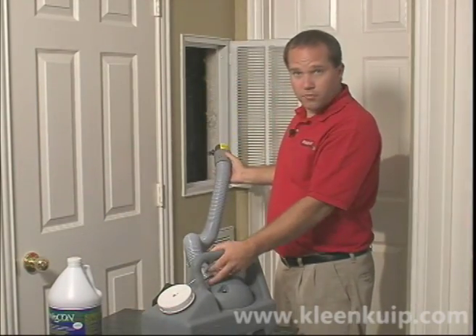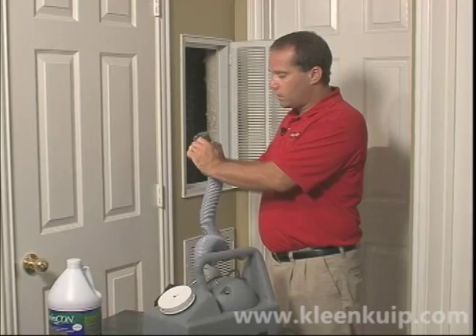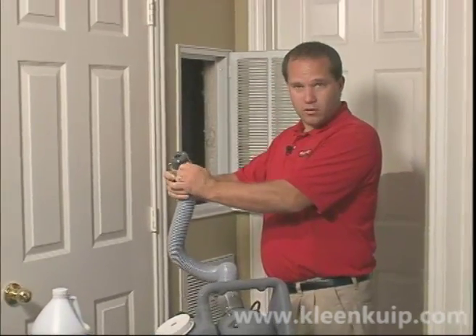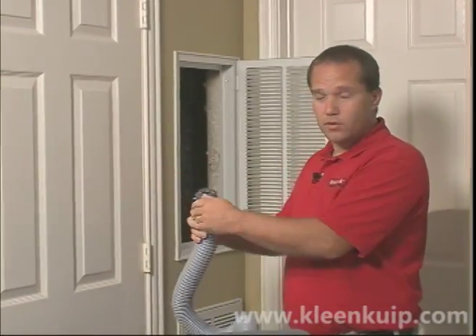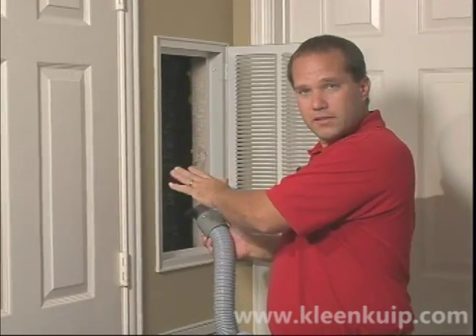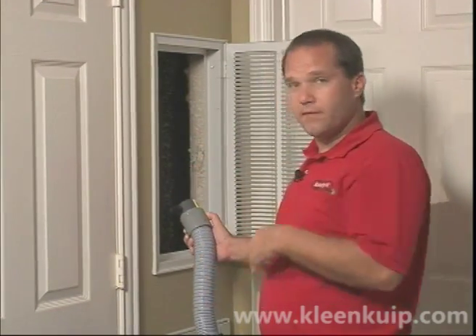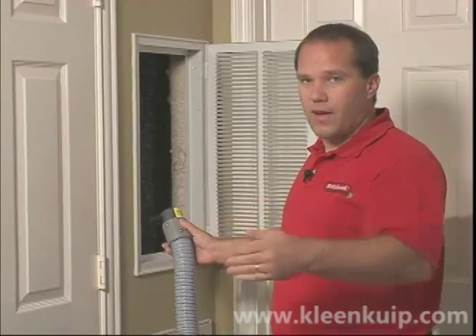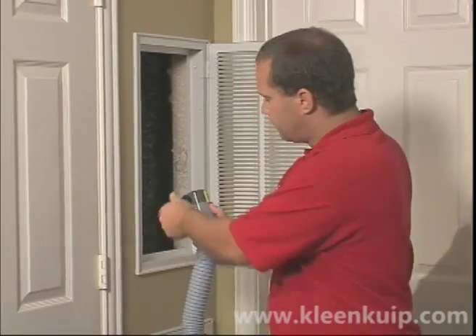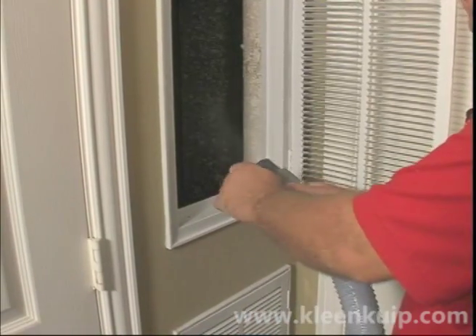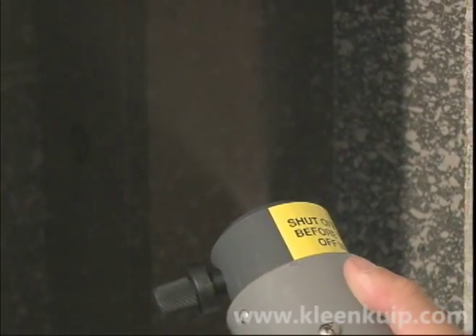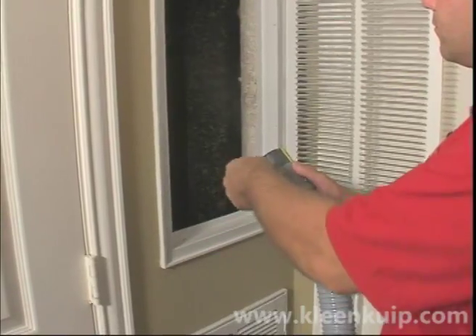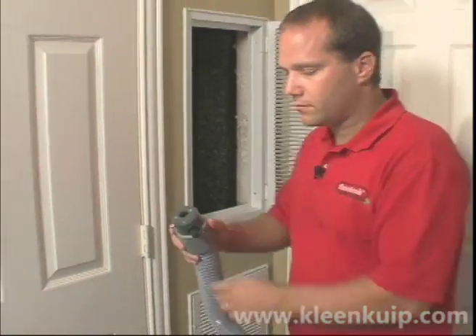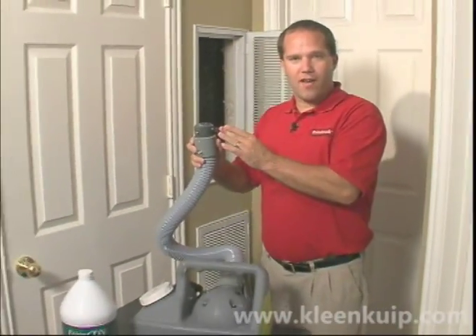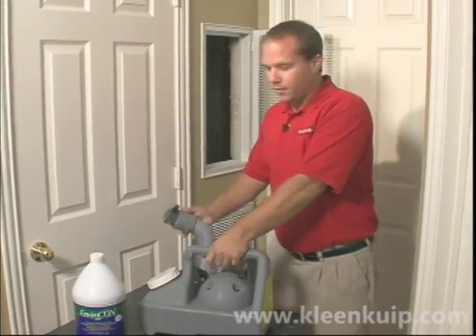and you have an on-off switch here and then a valve here. All you do is turn this valve counterclockwise until you see a light mist. Once you see the light mist, fog 45 to 60 seconds per 1,000 square feet of room space. If you have multiple returns, you divide that up between each return. Make sure you turn off the valve prior to turning off the motor to prevent spillage.